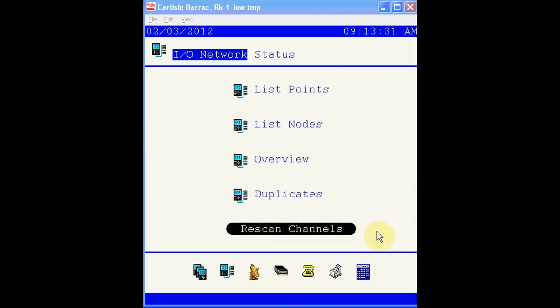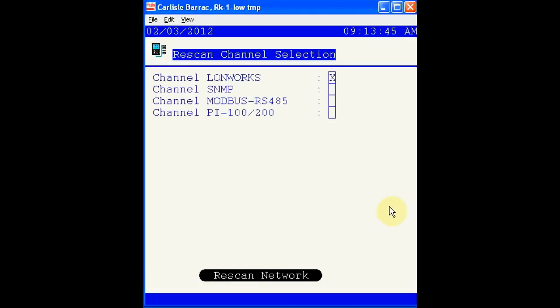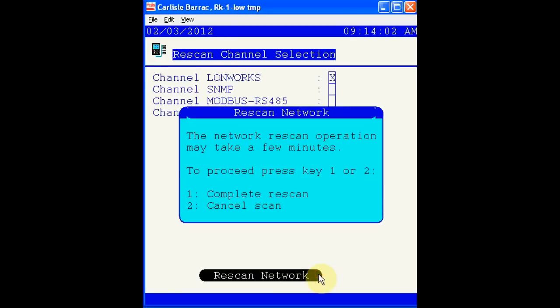If we back up to the I/O network status screen, we have the option to rescan channels. This would be done to bring boards online initially, or to re-establish communications with boards that may have gone offline. For most sites, the only selection that needs to be made on this screen at the top will be Channel LonWorks. This is based on the type of I/O boards that are installed. If we wanted to rescan the network, we would select the Rescan Network option at the bottom and press 1 or 2. If we chose 1, the top of the screen would give us status feedback on the operation. A typical rescan will be completed in less than 1 minute, and you'll be given a summary at the end of the rescan.